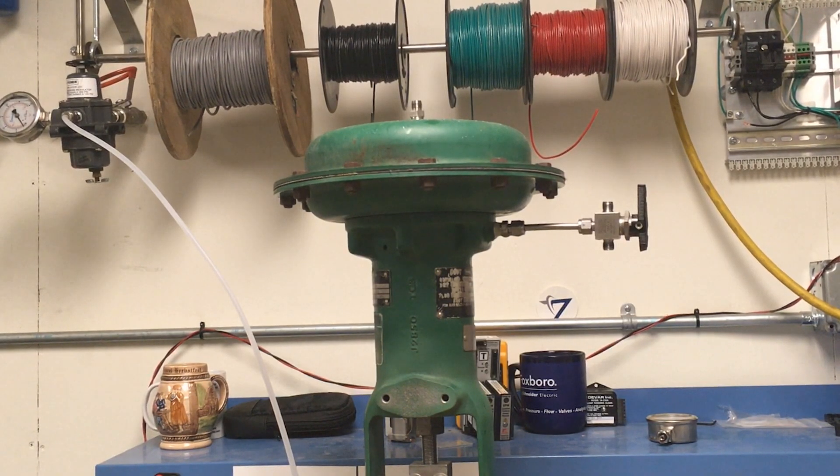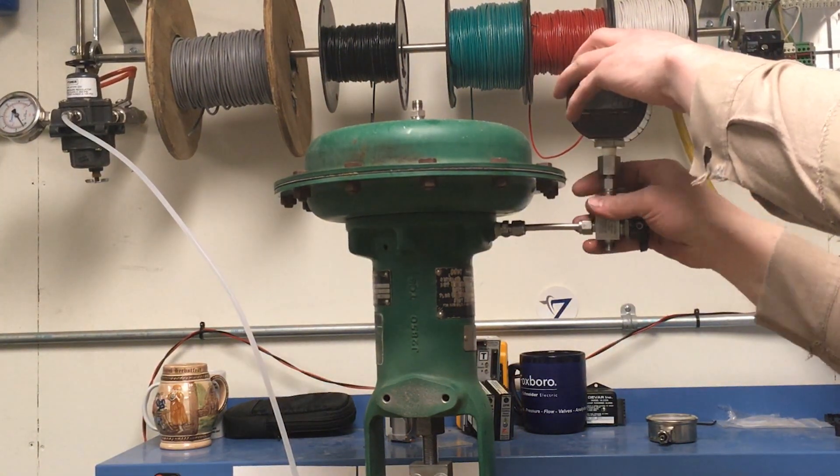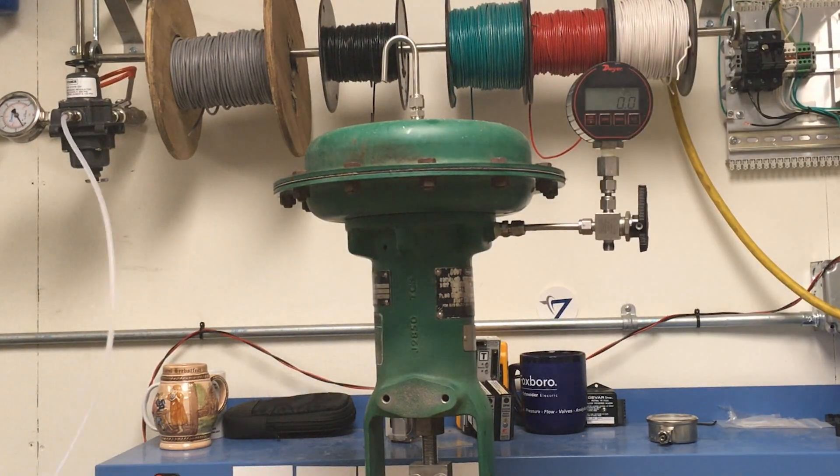To begin with, you will need to connect a three-way valve to the normal supply port of the actuator. We will be connecting a pressure gauge to one side of the valve and the pressure supply to the other side.